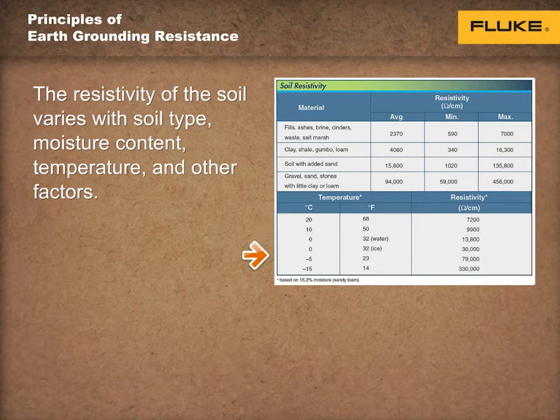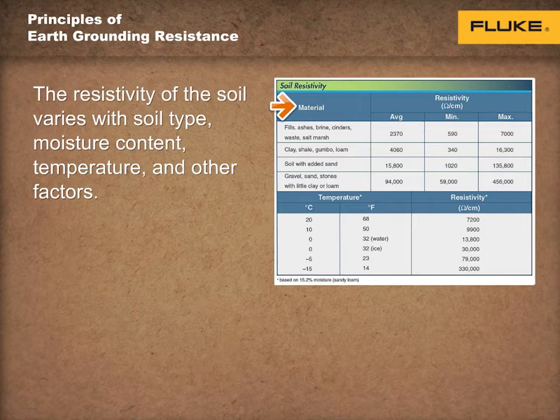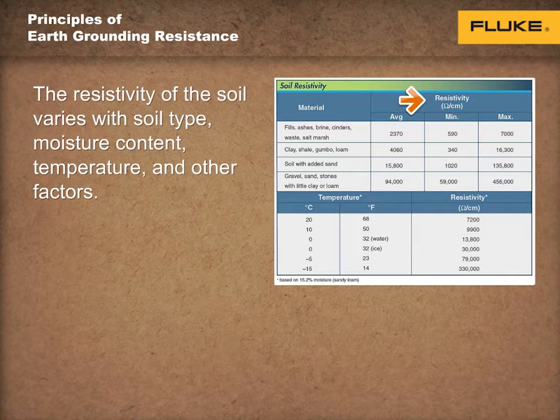Understanding the type of soil and its resistance also helps in selecting the material of the grounding electrodes. In general, the lower the soil resistivity, the higher the corrosiveness of the soil. Electrodes made of stainless steel or copper, either plated or solid, are the least affected by corrosion, and galvanized electrodes are the most affected over time.